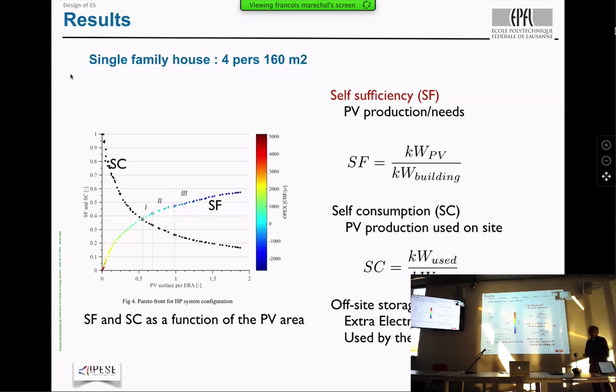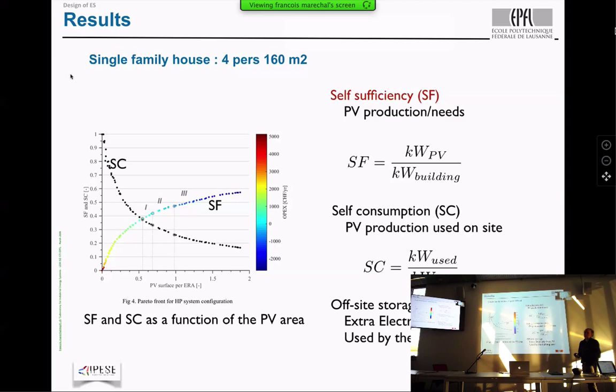And only 40 can really be used directly by you. And then we have made a strange calculation: what is the size of the battery needed to receive this 60% back, to be self-sufficient. So this 60% has to be sent to the grid. It will be considered to be stored in a very big battery, so that we can reuse it when we need it. And the two other points, 2 and 3, consider the efficiency of the battery: this is 80% and this is 55% round trip efficiency. So it means, of course, that if I have a certain efficiency in the battery, I will need more photovoltaic panels, and it will be even worse if I have a lower round trip efficiency.